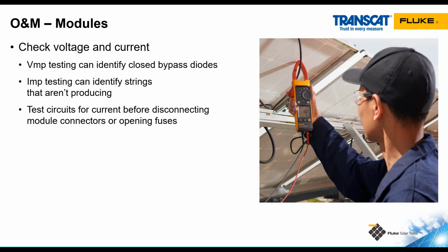I should also mention that when we're testing current in a solar array, especially with a string of modules or an individual module, we're never using the probes of a multimeter to do current testing, because anytime we put probes on a circuit that's energized to test current, we're short-circuiting that circuit through our multimeter. And as long as the current is below 10 amps, the multimeter will be able to read it. But the problem happens when you lift the probes off of that circuit, you're breaking the circuit, and it's going to arc. It's going to damage the test probes. It may damage the terminal, and it's a safety hazard for the technician. So we're always using a clamp meter like the one pictured here to measure current in a solar array.